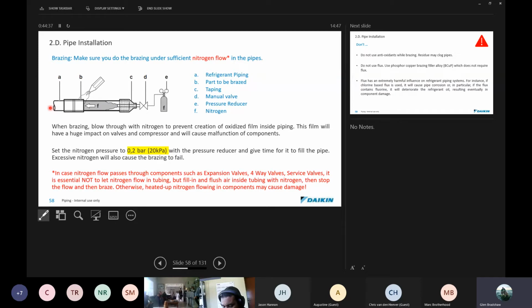It is also advisable on bigger pipes to tape up at least half the outflow so that we ensure that we fill the pipes up with nitrogen. On a bigger pipe, we may only have nitrogen flowing along the bottom, and that's not going to help the top of the pipe. We're still going to get oxidation there. So it is very, very important. If you don't braze with nitrogen, the oxidation and flaking that you get inside the pipes has a big negative impact on the oil and on working components like expansion valves. We also have a lot of strainers in the system, and those strainers can also block up.